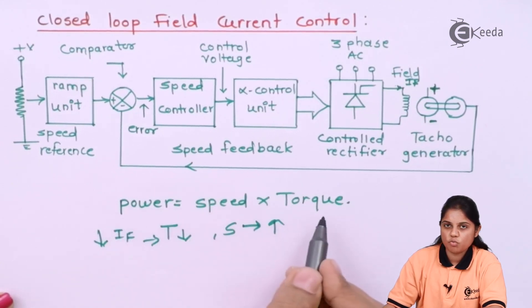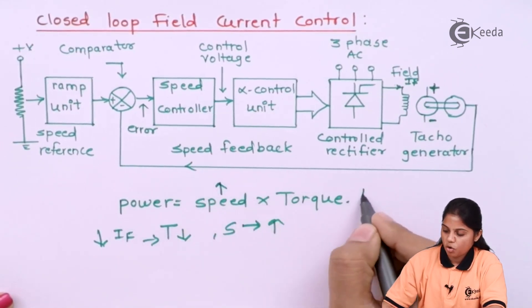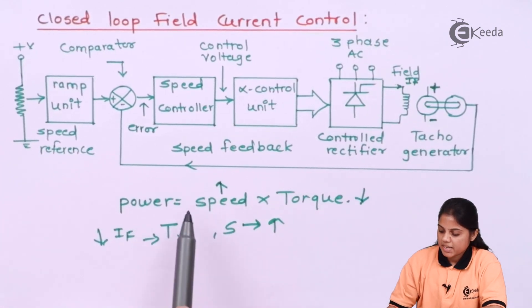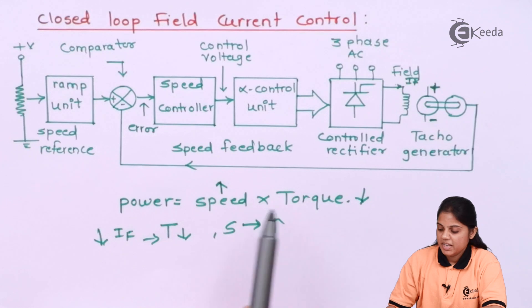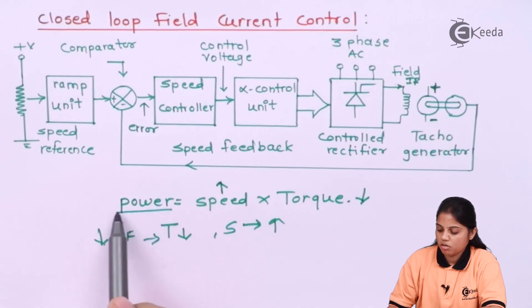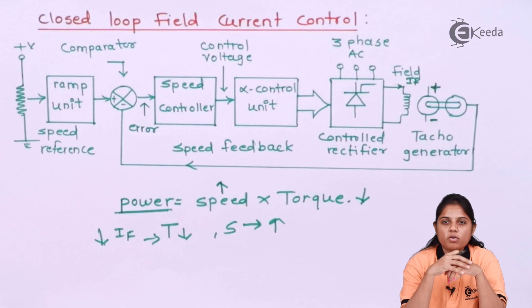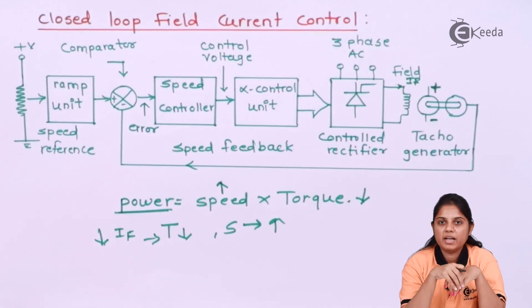Basically in this region, your speed is increasing and torque is decreasing. Because there is an increase in one parameter and decrease in one parameter, it will keep your power constant. Hence the region is called the constant horsepower region.